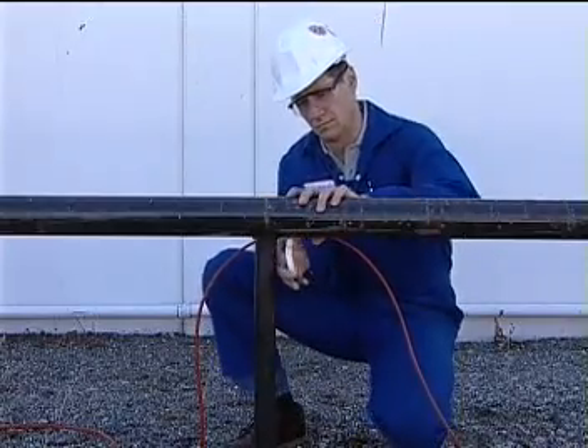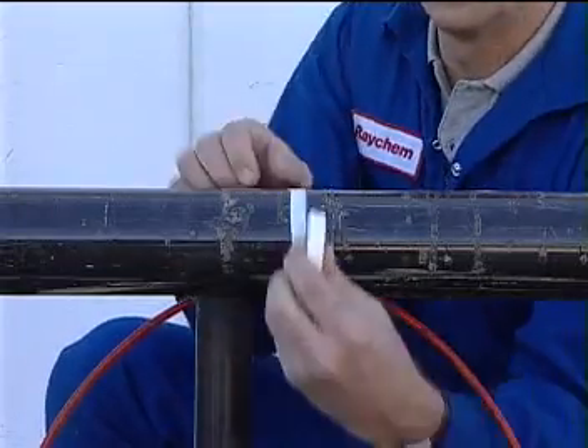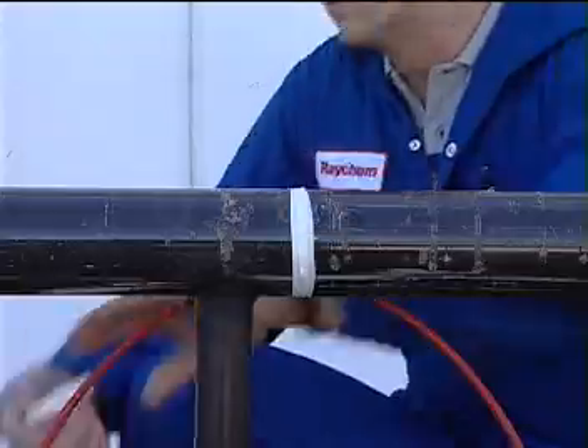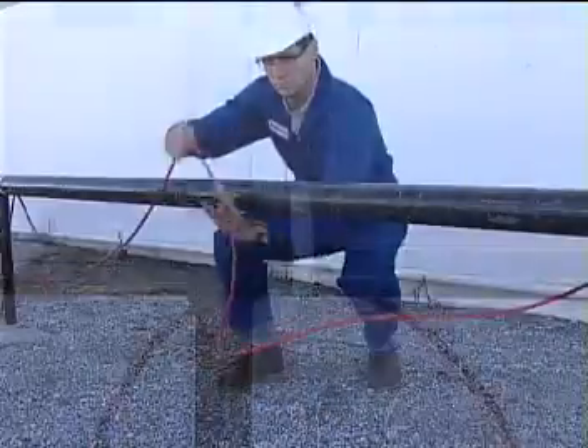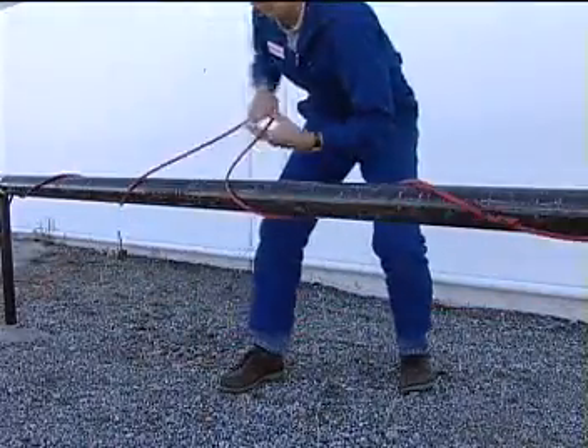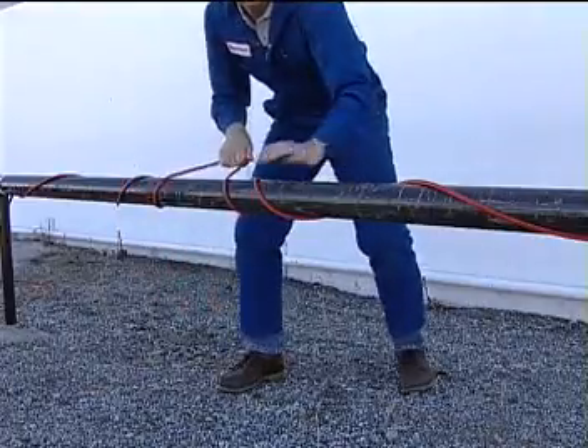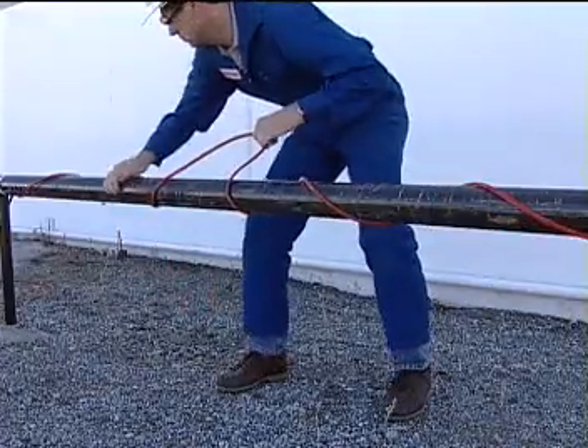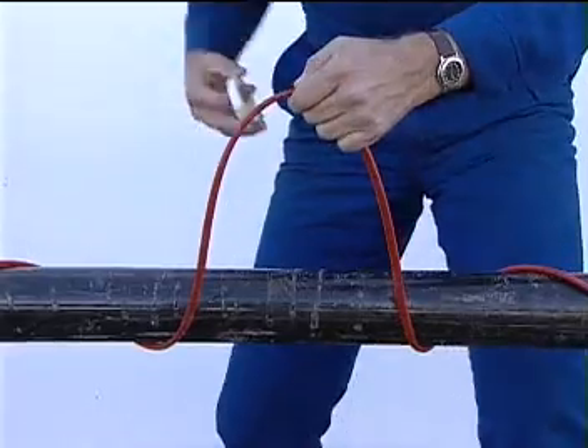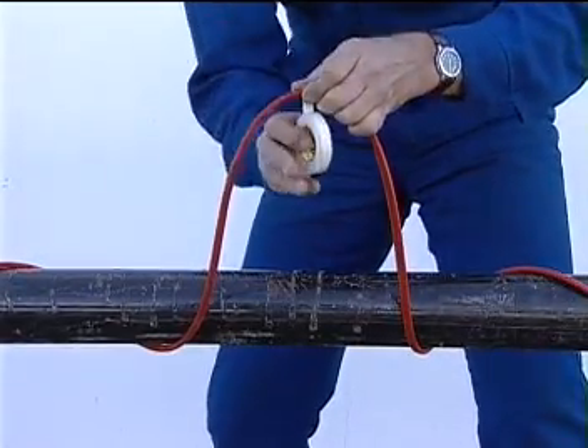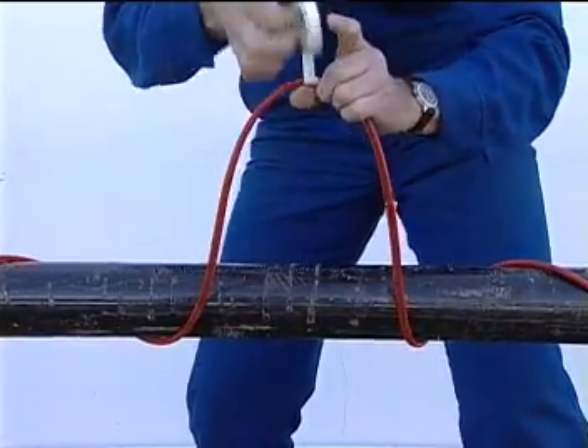For example, a heating cable ratio of 1.3 feet of cable for every foot of pipe would require 13 feet of heating cable for every 10 feet of pipe. Tighten the loop of heating cable around the pipe until all of the slack has been taken up. Then tape the final loop in place. Make sure that you trace the heat sinks as previously shown and leave service loops at the end of the cable.